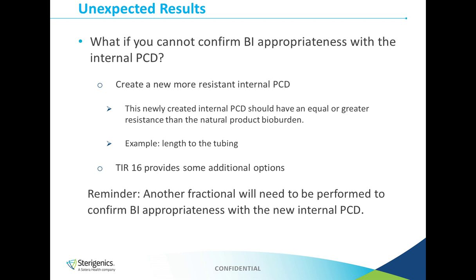Now you may be asking, what if I can't confirm BI appropriateness with the internal PCD? So if you don't get the results that I just talked about, there are other options. You can create a more resistant internal PCD. Now this more resistant internal PCD, again, has to be equal or greater in resistance than your natural product bioburden. And some options here are to include different devices that may be more challenging or adjusting your device to make that device more challenging, such as taking your tubing and extending the length or decreasing that inner diameter so that that sample would be used for your validation. It would be seen as worst case.